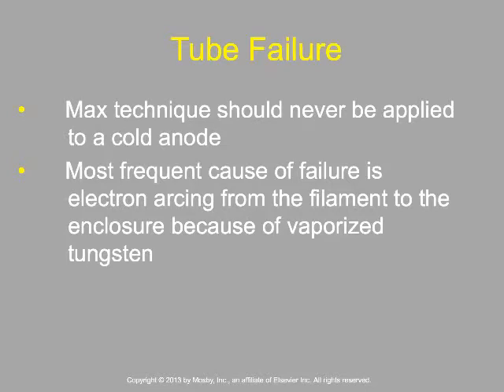A max technique should never be applied to a cold tube. Anytime we do experiments in the lab, we warm up the x-ray tube prior to making large exposures. When we don't heat up the tube and apply a max technique to a cold anode, we are much more likely to increase tungsten vaporization, which can cause electron arcing.